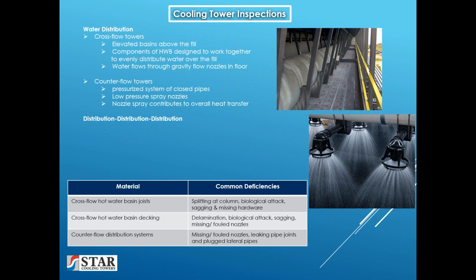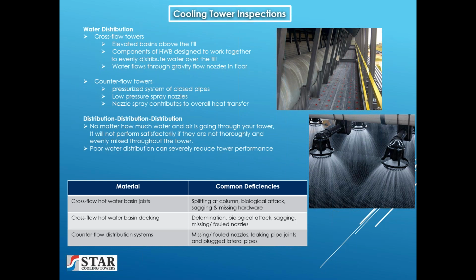So, distribution. The reason I say that three times is it's extremely important. No matter how much water and air is going through your tower, it will not perform satisfactorily if they are not thoroughly and evenly mixed throughout the tower. Poor water distribution can severely reduce tower performance. The importance of even and equal distribution of water cannot be overemphasized. And this is one of the least expensive maintenance items on a cooling tower.